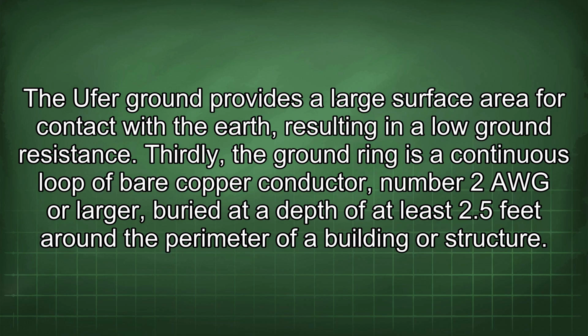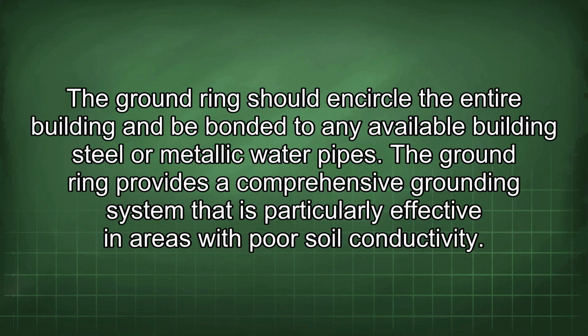Thirdly, the ground ring is a continuous loop of bare copper conductor, number 2 AWG or larger, buried at a depth of at least 2.5 feet around the perimeter of a building or structure. The ground ring should encircle the entire building and be bonded to any available building steel or metallic water pipes. The ground ring provides a comprehensive grounding system that is particularly effective in areas with poor soil conductivity.